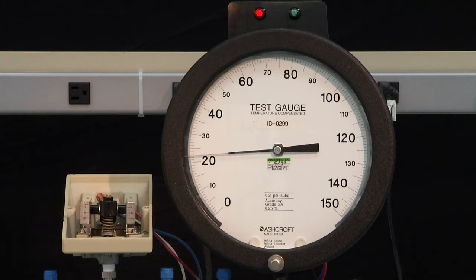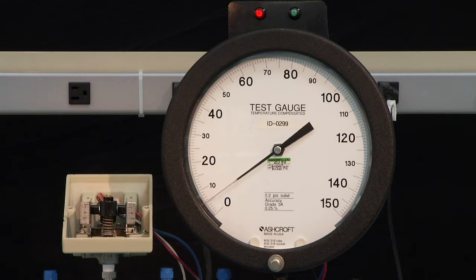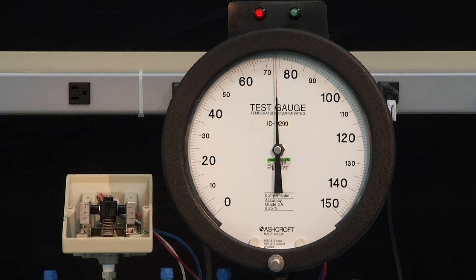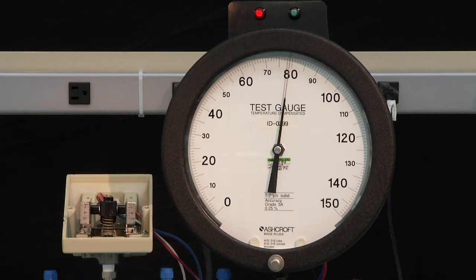We want to verify our set point by measuring it three times. We always go back to zero. And then we raise the pressure up to just before our anticipated set point, which we set up to 80, and then we slowly approach 80 and we should see the activation right on 80.